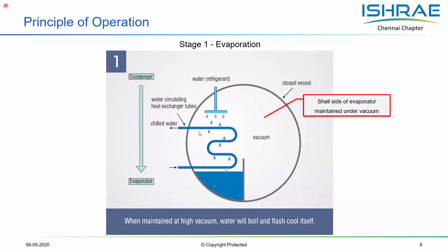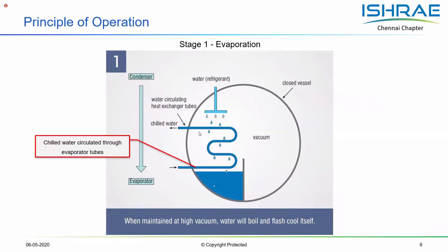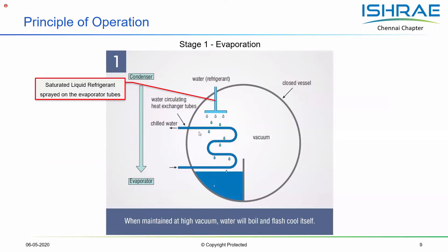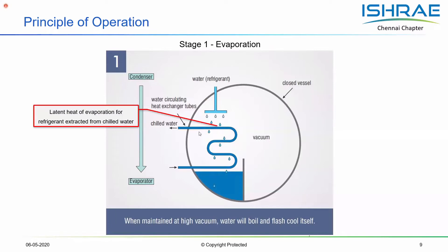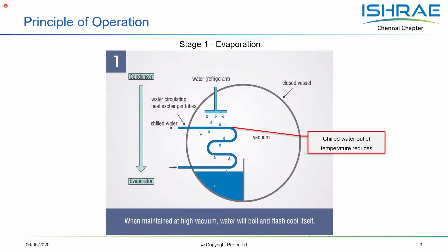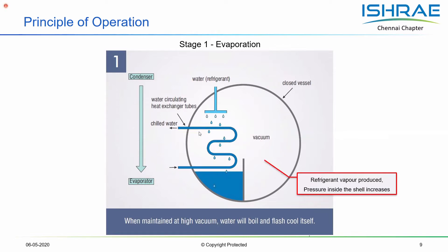To have this entire system working, we have to maintain vacuum inside the chamber, because at this particular vacuum only the boiling of the refrigerant takes place. The latent heat for this evaporation of the refrigerant is derived from the chilled water, like in any conventional refrigeration cooling system. The saturated liquid refrigerant is sprayed on the evaporator tubes, and when this water falls onto the tubes, heat transfer takes place between the chilled water and the refrigerant, which instantaneously evaporates the refrigerant. As a result, the chilled water temperature reduces and leaves the chiller at the required temperature.